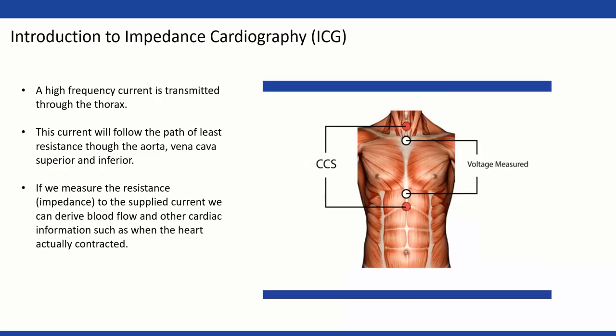Introduction to impedance. What we're doing is transmitting a high-frequency current from the back sensors — shown here in red. That current transfers through the thorax of the person and follows a path of least resistance, which, due to the blood, is mostly found in the aorta, vena cava — superior and inferior — all in the heart. The two front sensors then receive that current. Depending on whether there's blood or not, we know the resistance of that current, which is how we track blood flow — when the left aortic valve opens and when blood is ejected.